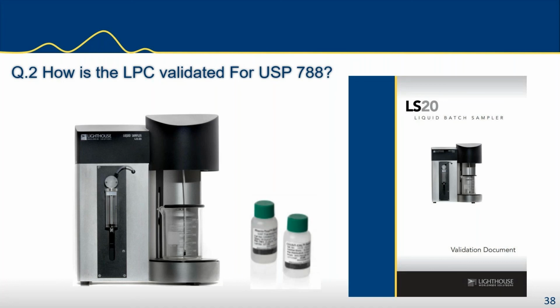So you can get test standards, test references, latex spheres, like these bottles down here, and they will have a known volume, a known concentration of particles at a particular size. For example, let's say these are 15 microns and you run them through the test. You'll flush out the unit, make sure you've got your blanks, and make sure that there's no contamination within the system. You basically would invert this 20 times, let it rest for a little bit, and make sure there's no gas bubbles. You will then put the sample into the inlet tube, take off the cap, and it will take a couple of volumes and calculate the average.